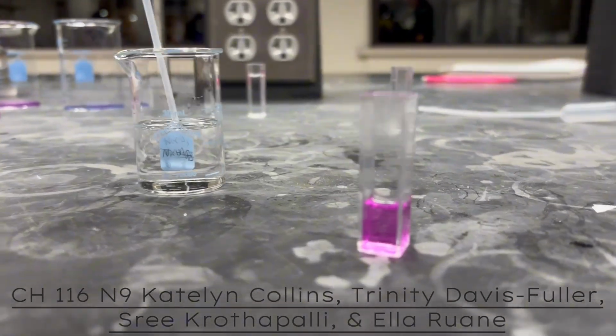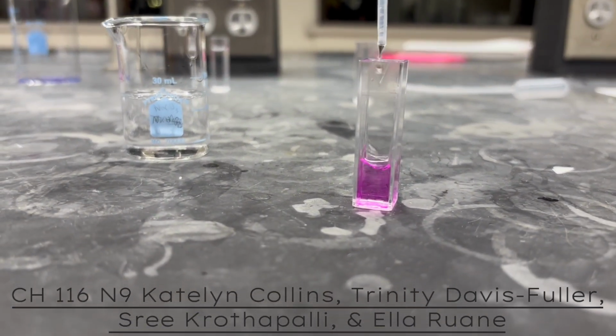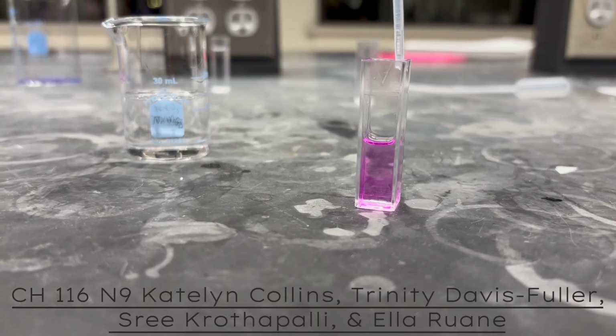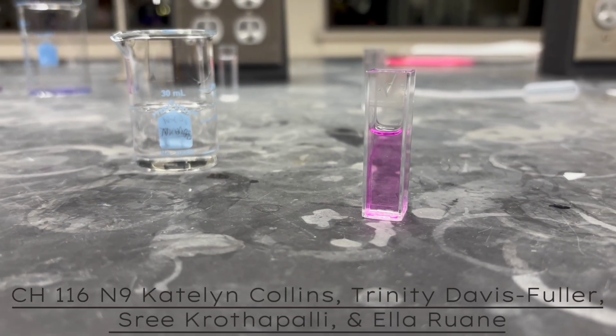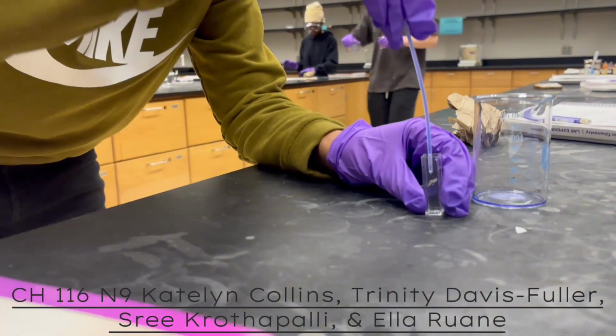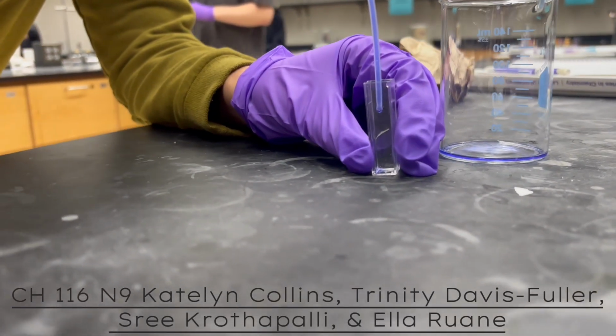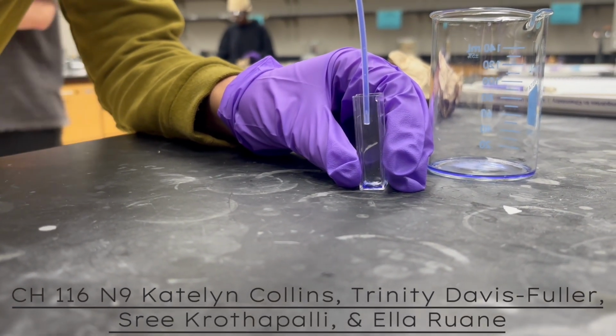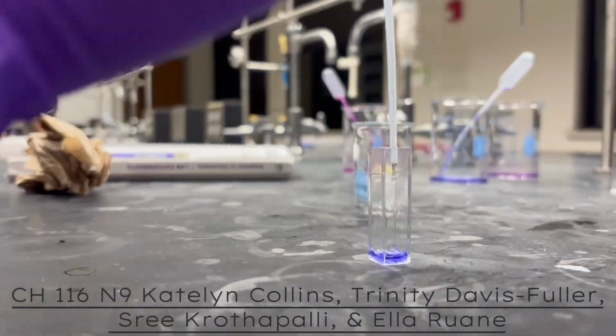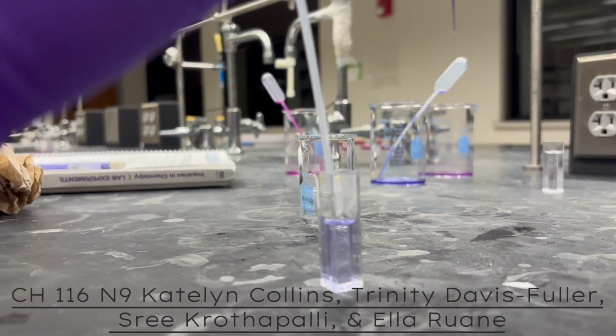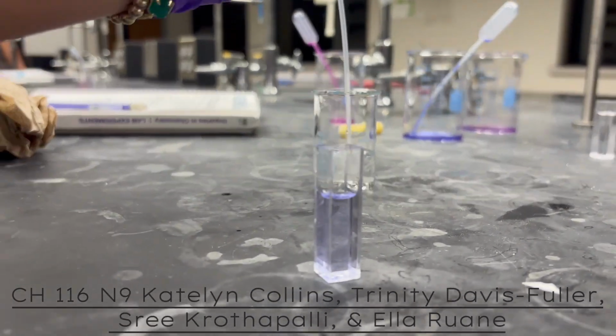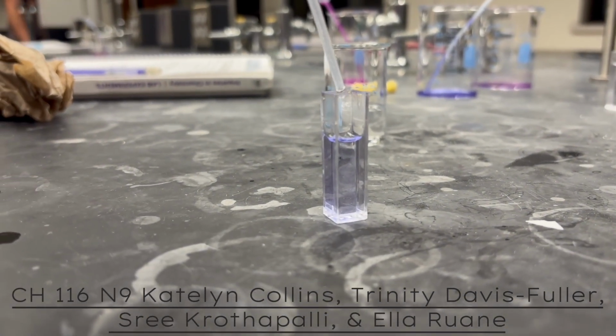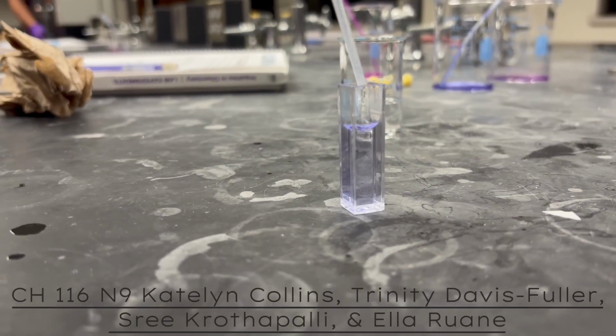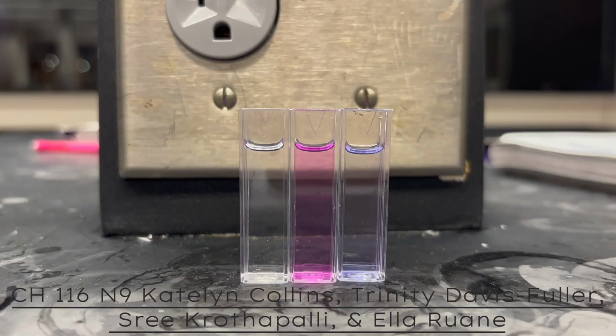The reason we do this is that different compounds will absorb light differently across the spectrum, and scanning across all wavelengths helps us to identify at what wavelength the substance will absorb the most light. Secondly, this is to aid in detecting impurities or multiple absorbing species in the solution. Samples won't always be pure. Reagents can break down, contaminants can make their way into it, or some of its other components absorb light as well.